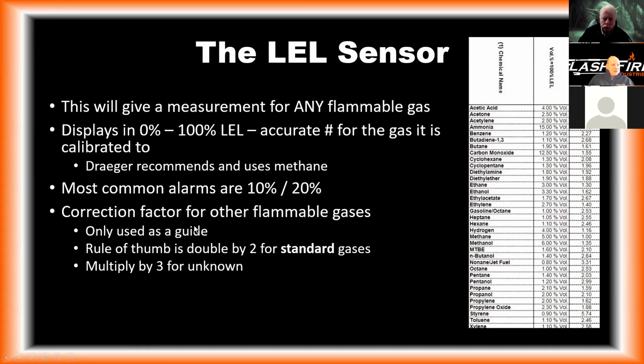Now, correction factors. You can take this as deep as you want to. I will show you how to use it. But again, it's not something that we're going to be doing on a daily basis for a couple of reasons. Correction factors are used as a guide. The rule of thumb is you take the number that you have on the LEL. If it's not methane, but it's a common gas that you've heard of, you double it, you multiply it by 2. And if it's a gas that you haven't heard of, multiply it by 3. And I'll explain that on the next slide.